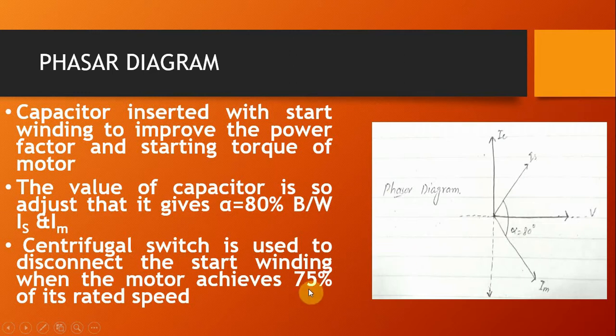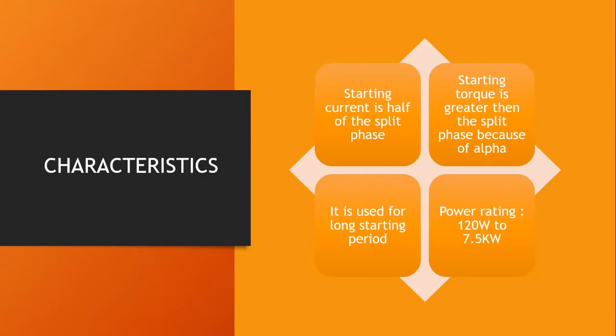Similarly, a centrifugal switch is used to disconnect the starter winding when we achieve 75% of the rated speed. A characteristic of the capacitor start induction motor is that the starting current is half of that of the split phase motor, meaning the current is decreased.